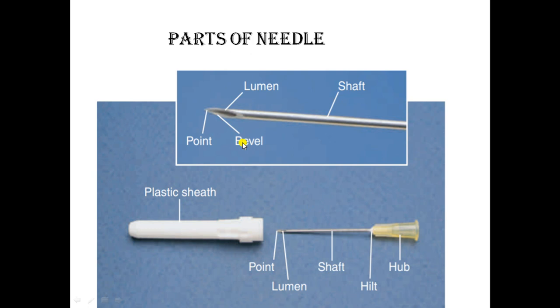The bevel helps ease insertion of the needle into tissue. There are finer cuts of different bevel lengths — for example, a fine-tip bevel is used for insulin syringe needles. The finer the bevel cut, the less pain and trauma to the patient's tissue. The shaft is the hollow steel part of the needle through which medication passes into the patient. The hub is the component that attaches the needle to the syringe and is color-coded for easy recognition of size.